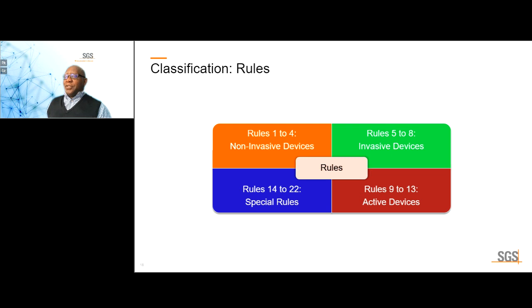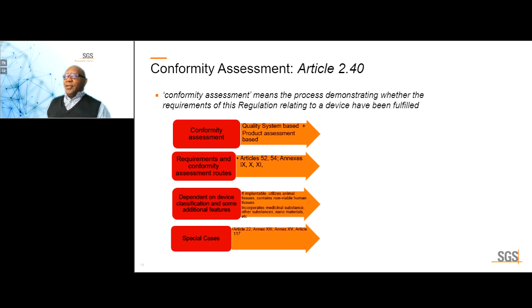Once you know these rules, then you have to classify your device. And you've got to keep in mind that if you think there are 2 rules that could be applicable, the rule of thumb is you will always default to the one that gives you the higher classification. That is because the authorities would rather manufacturers err on the side of caution.